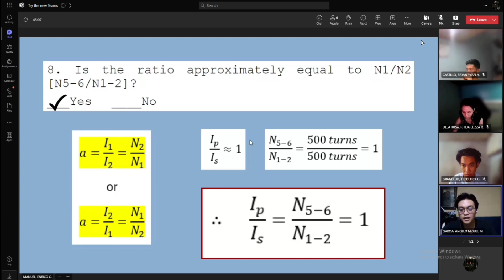So, why do we do the transformer short circuit test? Well, the slight difference in current readings between the primary side, which is 4.183 amperes, and the secondary side, which is 4.170 amperes, can be attributed to measurement inaccuracies or small losses in the transformer. The ratio of the primary current to the secondary current is calculated as approximately 1.003, as said by my fellow groupmates. This indicates that the primary current is approximately 1.003 times the secondary current, which is very close to 1, and this small discrepancy is within the expected range of a well-functioning transformer. The purpose of the short circuit test is to determine the copper losses of the transformer.